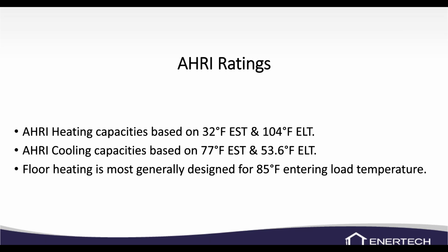AHRI ratings, we'll show it here in the next chart, but basically the heating capacities are based on 32-degree entering source temperature and 104 entering load. And on cooling, it's 77 on the source and roughly 53 on the entering load temperature. Normally, they design the floor heating for around 85-degree entering load temperature. So we're leaving about 90, 95 degrees.